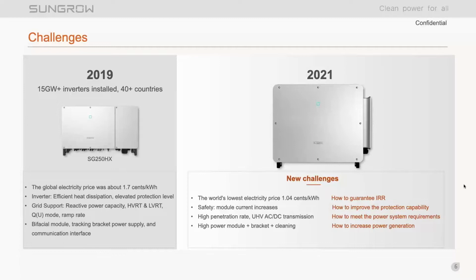The growing capacity of photovoltaics, coupled with the volatility, unpredictability, and emergence of new energy, are having a progressively adverse impact on the power grid. So as a result, for us that are technically minded out there, short circuit ratios of power conversion equipment are gradually declining. So we're designing our inverters with adaptability in mind to better support the grid against these more common conditions. Continuing the evolution of this grid reinforcement by PV inverters is now a problem that we're actively solving, not one that we're retroactively trying to keep up with. And it's definitely one that is Sungrow's charter as we navigate this ever-changing ecosystem of renewable energy generation.